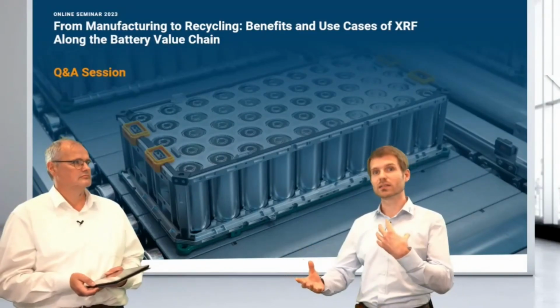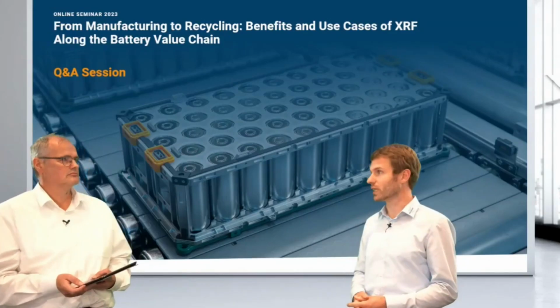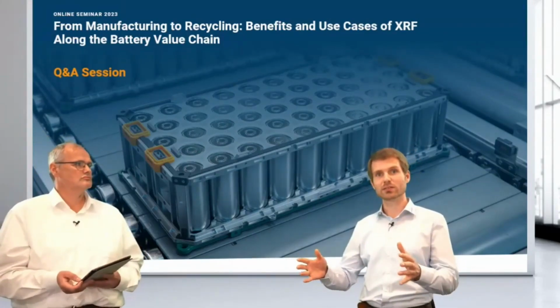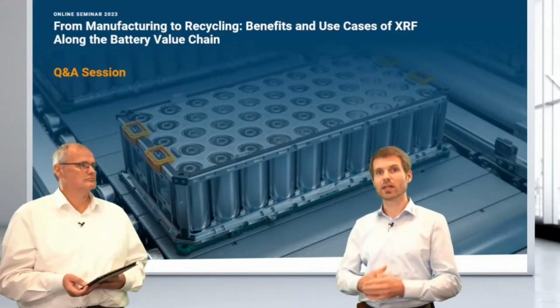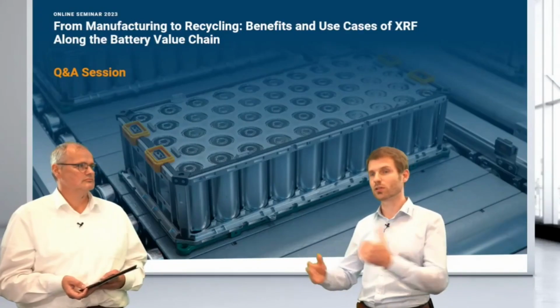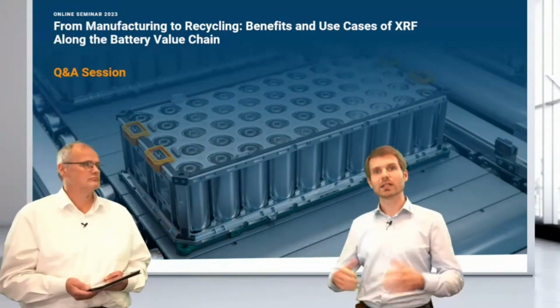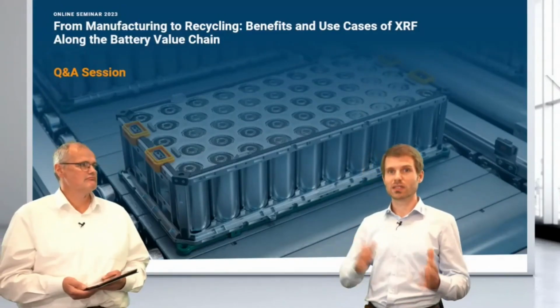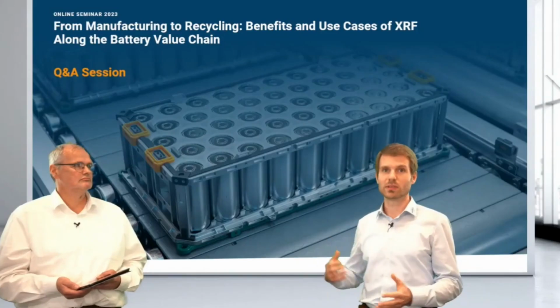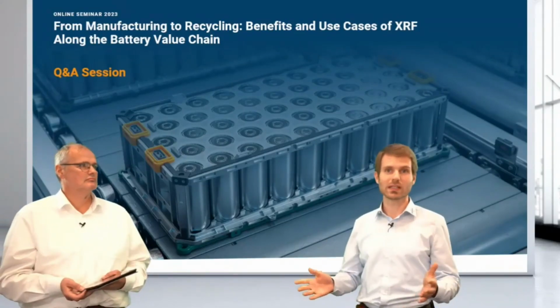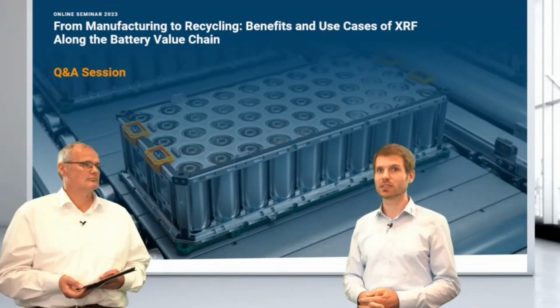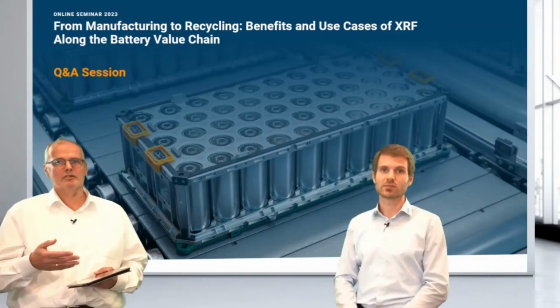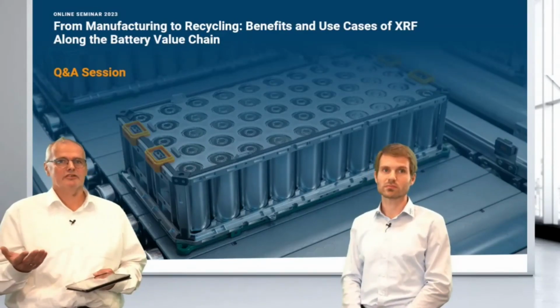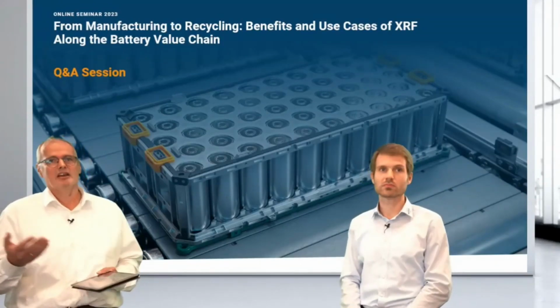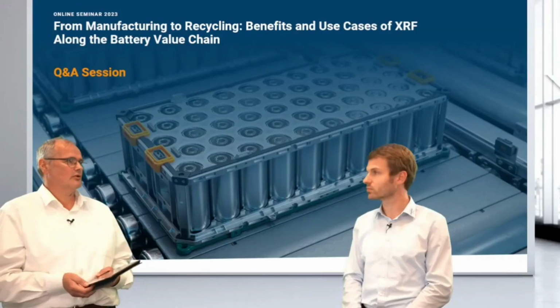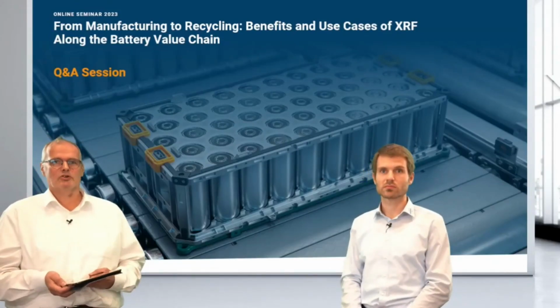The point is how reproducible your grain size is. If it's a really wide spread, sometimes more coarse, sometimes finer, then we would recommend putting it on a common ground, so basically grinding it. The materials we've come across so far, like black mass from recycling or precursor material, are typically suitable as is, so we haven't come across many challenges with grain size. When we have a very good material, we are at a range of 0.05% relative at best. It might be slightly less accurate for major elements the moment the material is coarser.